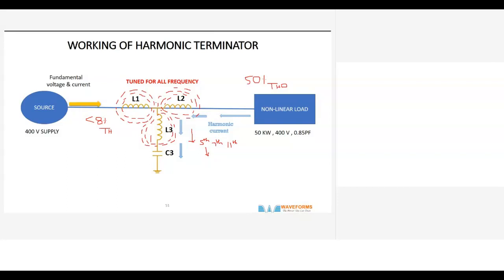Now the special thing about this capacitor is we use a very small capacitor, maybe just 15% of the total requirement. Suppose the non-linear load requirement is say 100 kVAR or something. We use only 15% capacitor because most of the harmonics is mitigated here. So we need it just for the residual. We are having a filter only for the residual harmonics.